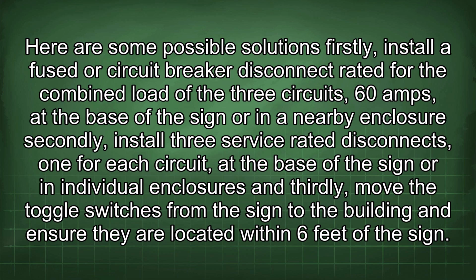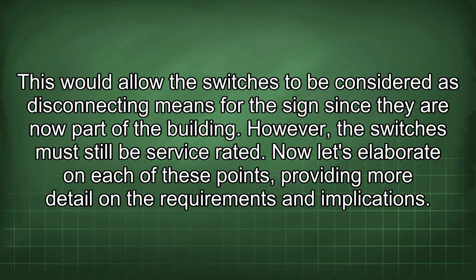And thirdly, move the toggle switches from the sign to the building and ensure they are located within 6 feet of the sign. This would allow the switches to be considered as disconnecting means for the sign since they are now part of the building. However, the switches must still be service rated. Now let's elaborate on each of these points, providing more detail on the requirements and implications.